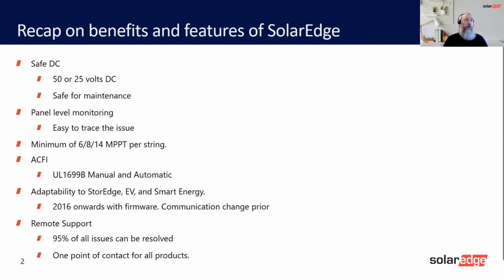With the panel level monitoring, it's very easy to see which modules are shaded, which modules have module mismatch. So as you know, every module has plus or minus 3% energy difference. And if it was a traditional system, you'd all be operating at the lowest performing module. So SolarEdge allows each panel, each module, or each pair of modules to work at their optimum performance.